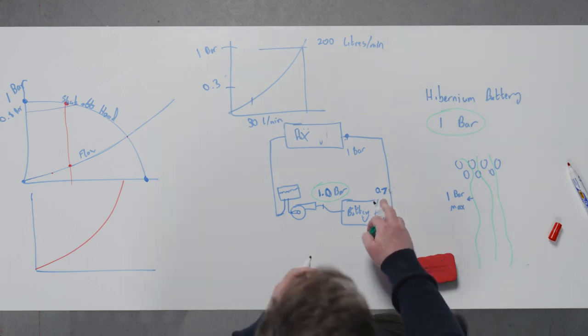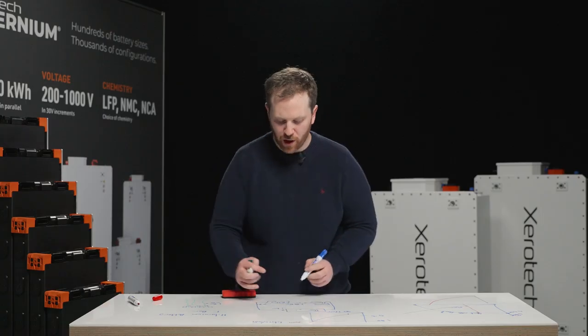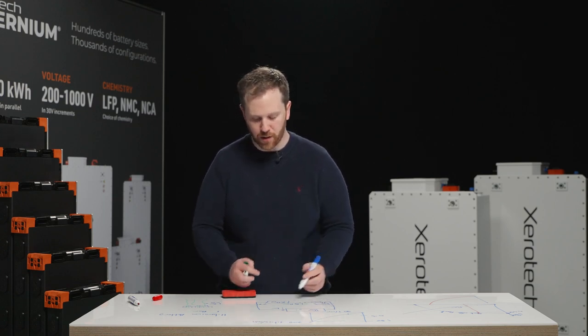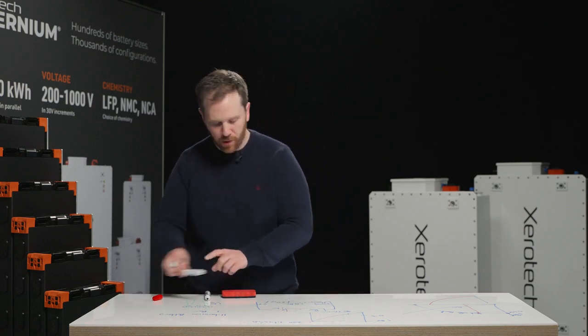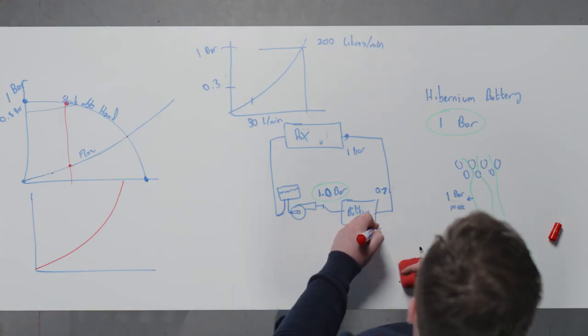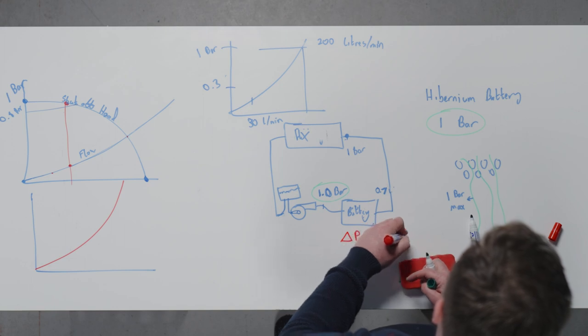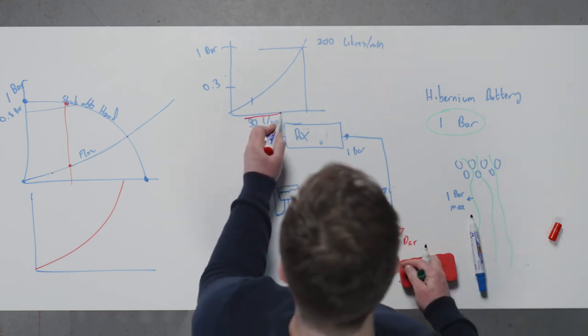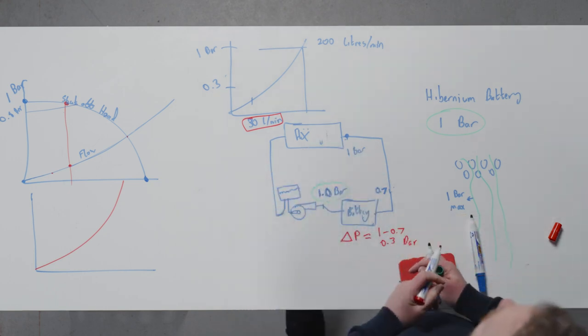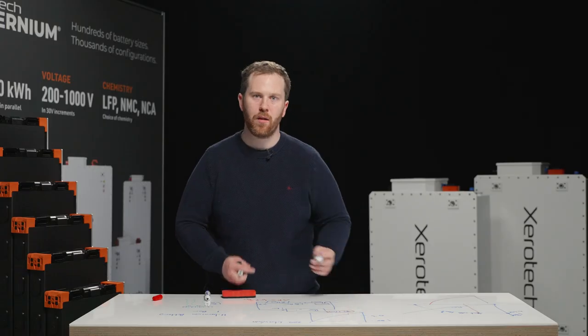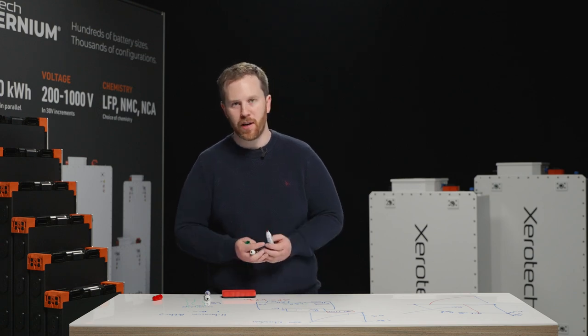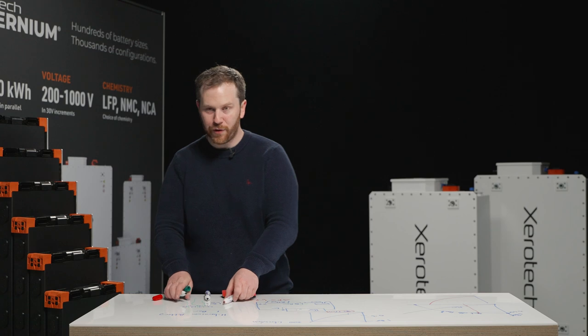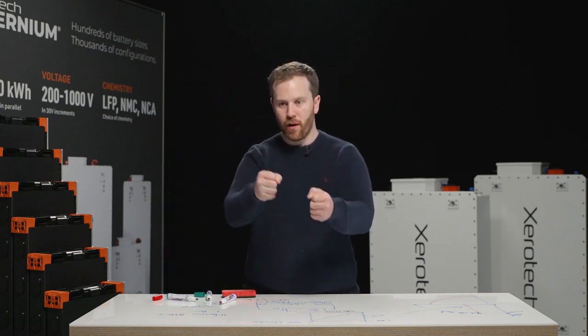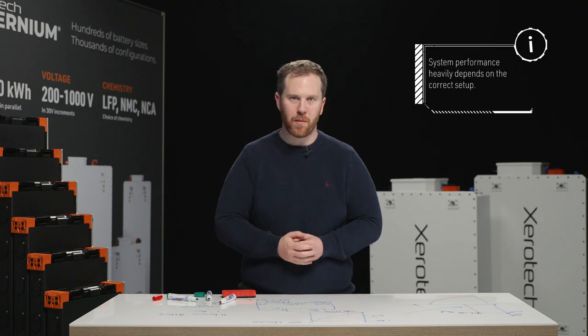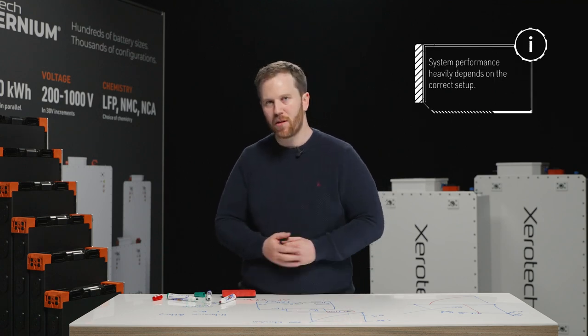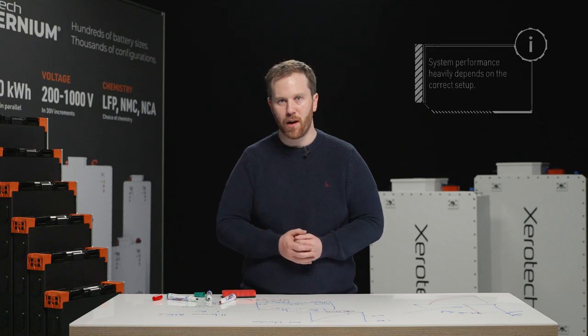And how you develop flow rate here is a difference in pressure. In the original scenario here, we had a pressure difference of 1 bar across the battery. In this case here, we've only got a pressure difference of 1 minus 0.7, 0.3 bar. So now you've got a system that can only have 30 liters a minute going through it. That's an order of magnitude lower heat transfer, flow rate, temperature spread in that battery pack, with the simple difference of taking a pump and moving the 2 coolant lines from this point to here. You reduce system performance by an order of magnitude. So it's really important to get this stuff right to maximize the thermal performance of your battery system.